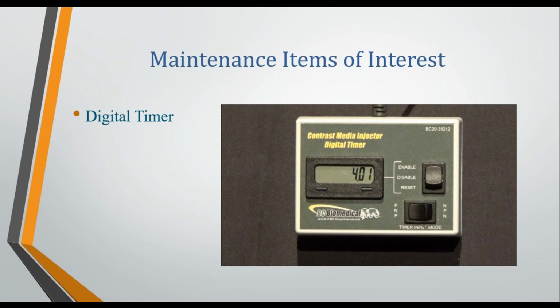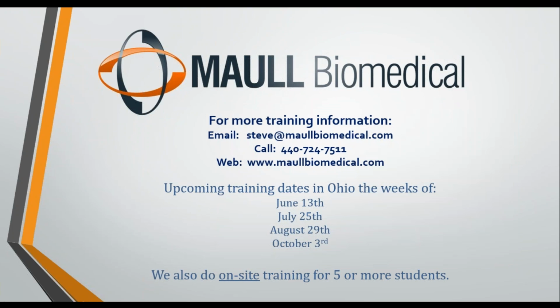Unfortunately for the angiographic injectors, just a stopwatch is not good enough. The time tolerance for the angiographic injectors is you're shooting a 4-second injection, and it has to be within 0.02 seconds. So just a handheld stopwatch is not reliable enough. You have to electronically connect the digital timer to your test points on your angiographic injectors to accurately measure a 4-second injection, again, plus or minus 0.02. So this is the only thing that is different between a Tier 1 test kit and a Tier 2 test kit. I hope that was helpful.